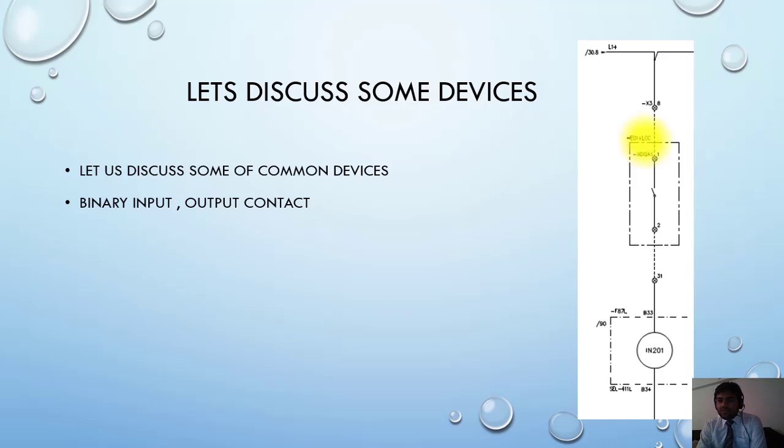One auxiliary contact - when it's closed, it will energize this binary input. For example, if I configure this contact when the breaker is closed, so this will close and I will get the signal in the relay to ensure that breaker is closed. So in this way this drawing will work.